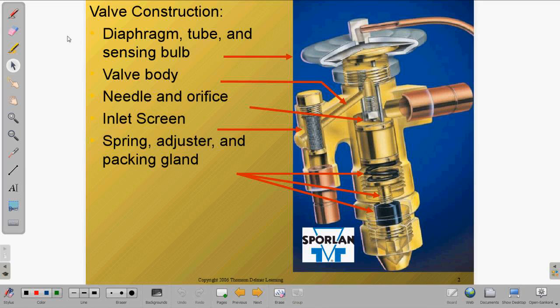Now, here is a cutaway view of a TXV valve, and a couple of things to point out, and you can see all of the different parts of it, but let me just show you how this works. The refrigerant, and we're going to go into this in detail, but I'll just show you the path. The refrigerant comes up this tube. There's the screen right here that you see. This filters out any large debris, and this is sometimes an issue with the TXV valve if it gets plugged up because of a bad installation. Usually that doesn't happen. The refrigerant flows through, and then it flows down through the needle and orifice, and then out into the evaporator coil.